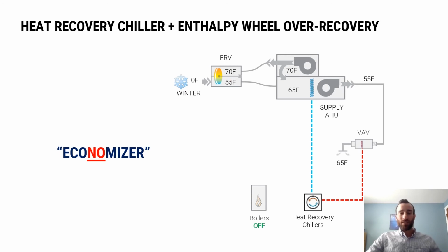The last type of exhaust source heat pump I want to go over is when we use an enthalpy wheel in combination with the heat recovery chiller. So this is applicable to mixed air systems like we would see potentially in a hospital. So normally, if you have air coming into your mixed air in your air handler that's too warm, what's conventionally done in the winter is you would open an economizer damper and purposely bring cool air into the system to cool down that air. That is an extremely stupid thing to do in the winter. We're purposely bringing cold air into our building.